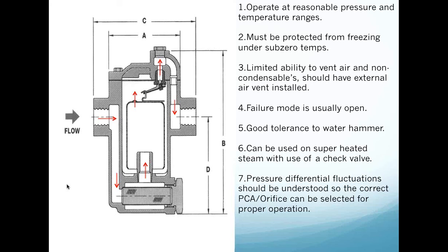So what happened now was that they had a large population of inverted bucket steam traps, which is absolutely fantastic because these devices have worked for years and years and years very reliably. Unfortunately, what they did not remember is that the actual capacity of those traps is predicated on that differential. And when you exceed the differential of this inverted bucket steam trap, the trap actually stops functioning. So they banked and built condensate up, and they had a condensation-induced water hammer event that blew up some valving components, and they had a major incident. It is very, very important to remember that if changes take place inside the system, you all stop and consider what exactly is it that I have in my inverted bucket trap population for differentials.